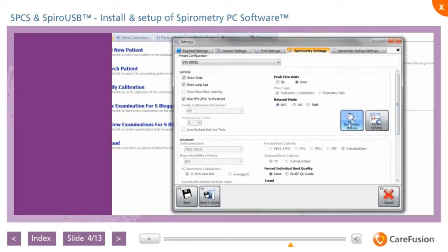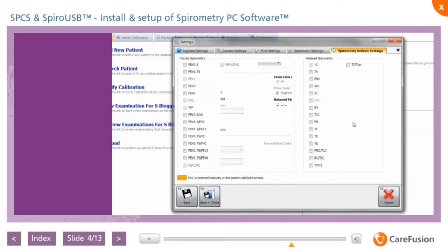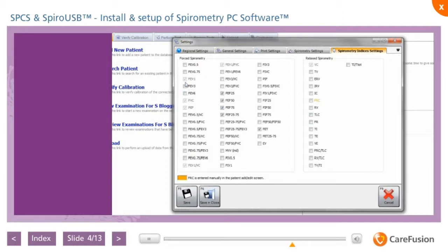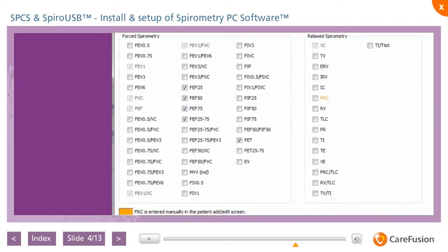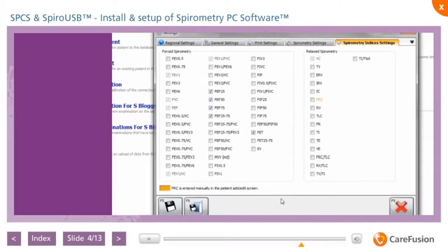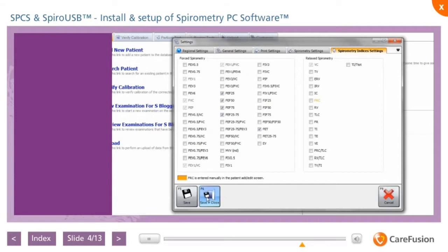The spirometry indices for both relaxed and forced maneuvers are listed for the user to decide which of them should be displayed in the software and printed on the report. Clicking on the corresponding box tick will generate a tick that confirms that the chosen indice will be included. It is entirely up to the user to decide the number of indices to include. It's important to note that all indices are calculated, which makes it possible to return to the indices setting after a test and increase the number of indices displayed and reported. Once the selection has been made, it should be saved.